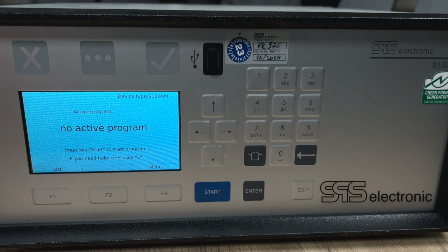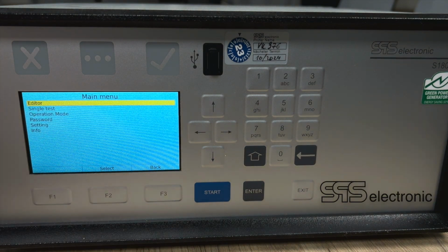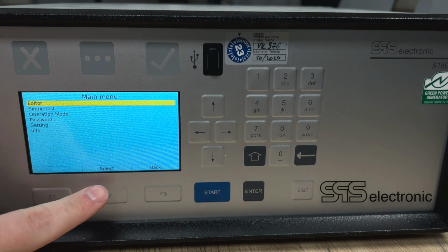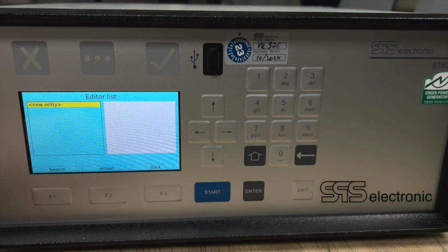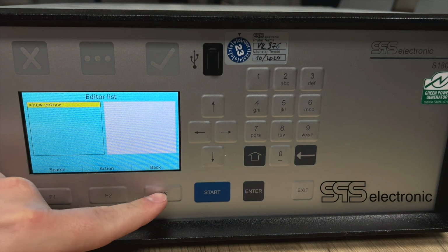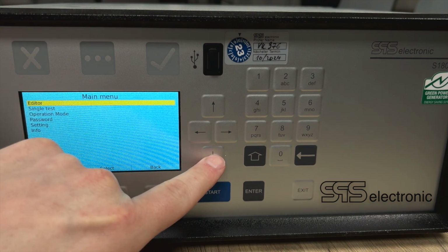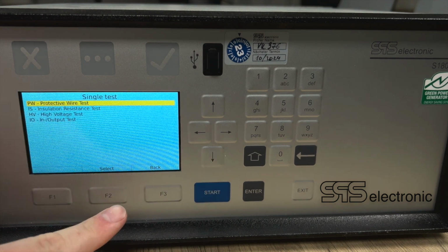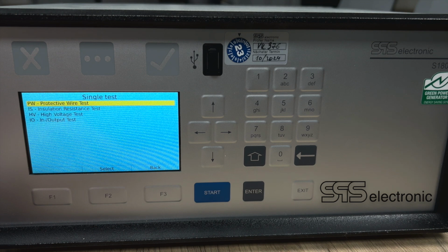From the main screen, we will go to menu. Here is the list of things the tester can do. The first one is editor, where we can create or choose existing test programs. The next one is single test, such as protective wire test, insulation test, high voltage test, or input-output test.